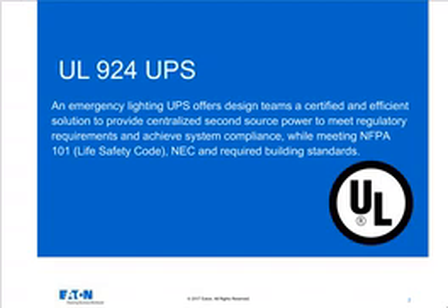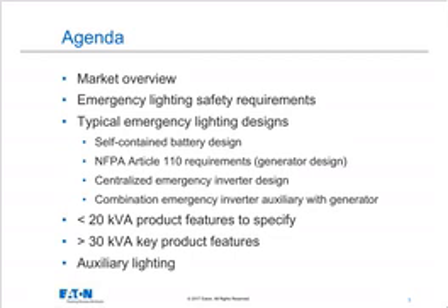So we want to be aware of that, and we'll take a quick look at our agenda, which is on the next slide. We're going to get a quick overview of the market here, talk about safety requirements that emergency lighting systems dictate, the types of different emergency lighting systems, because there's several ways to do this that are acceptable to the electrical code and fire code, etc. If I have relatively small lighting systems for a small to medium-sized building, that's generally going to be less than 20 kVA in terms of total UPS power.